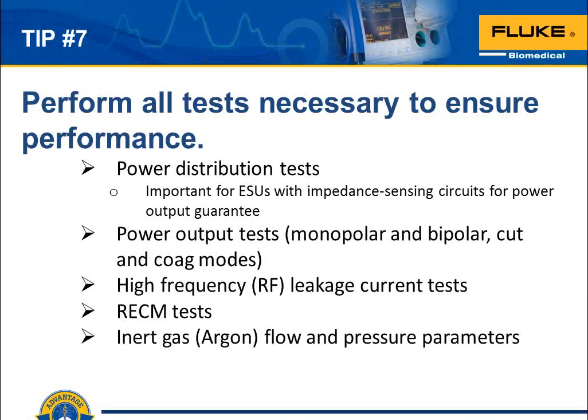Tip number 7, perform all tests necessary to ensure performance. So we've already listed these before. We're just going to run through them again. Output power tests for sure at several different settings. Usually manufacturers will recommend those in the inspection procedure or in a category-specific procedure. You're going to come up with your own. Whatever ones you're using, always use the same ones every time you go through and do that test. Power distribution test, as I said, mainly for those ESUs with impedance sensing circuits for power output guarantee. You're really going to want to run the power distribution test for those. Or by some means, test the same output energy across several different test loads to make sure that those circuits are keeping that output power where it belongs.